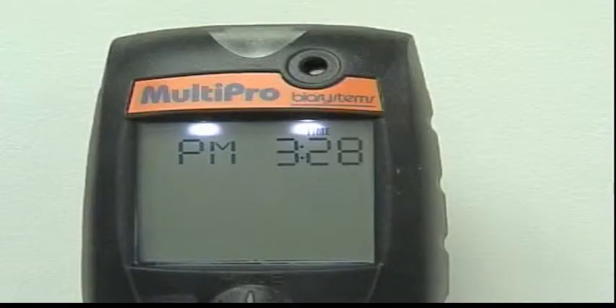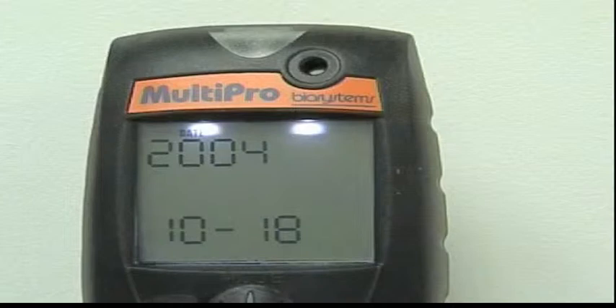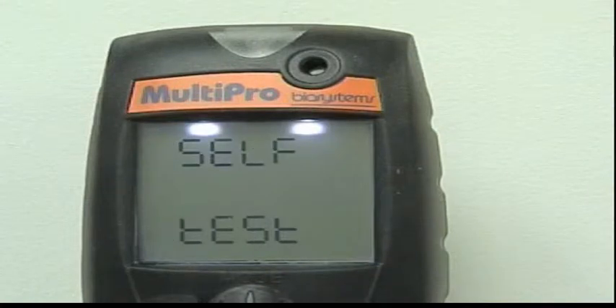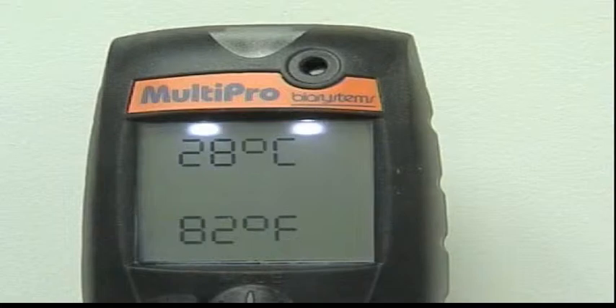The time and date will then be shown. Time and date settings can also be modified with Biosystem's BioTrack program using a PC with an IRDA port, or can be modified directly with the mode button on the instrument. The self-test screen will then be shown. During the self-test, the MultiPro checks for installed sensors and performs a system memory check.